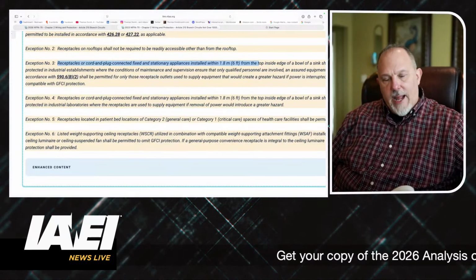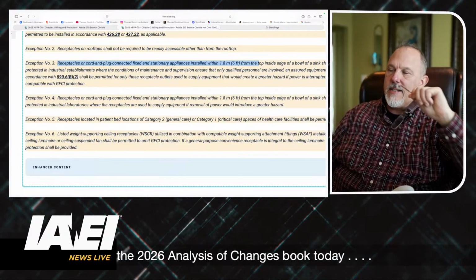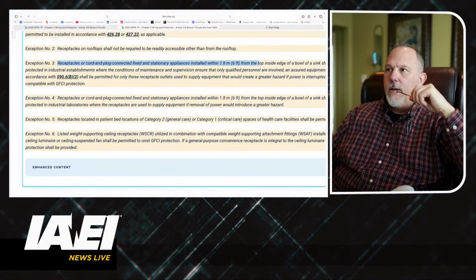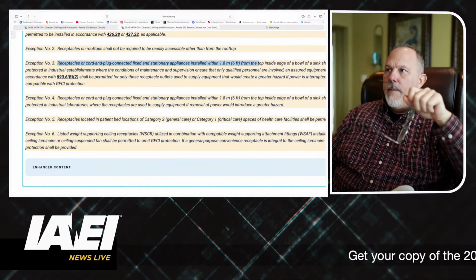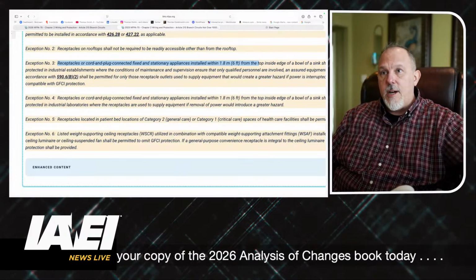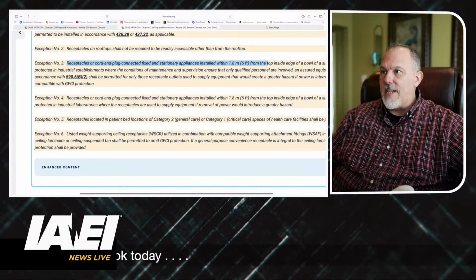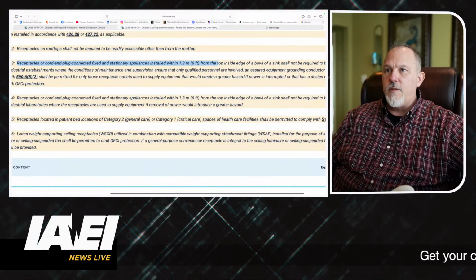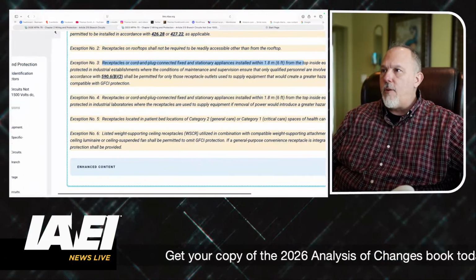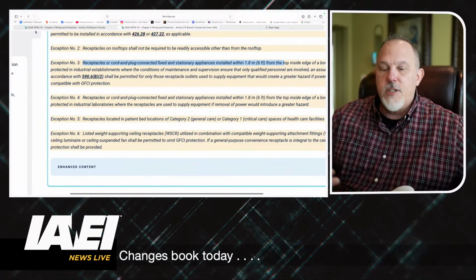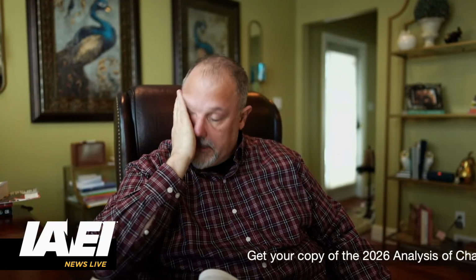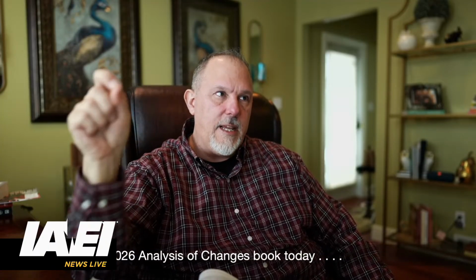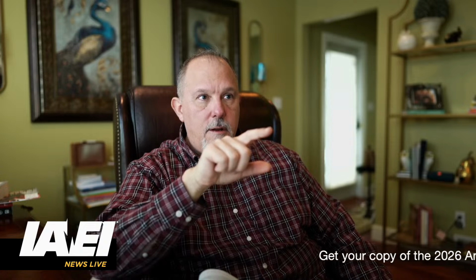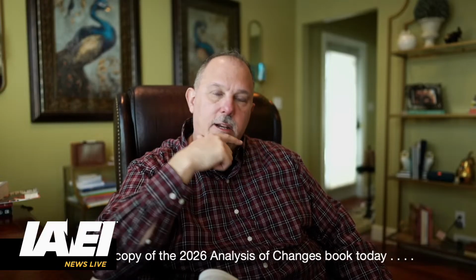So let's break this down. And it was during our task group meeting that I don't know who it was, read this and said, if I just forget about the cord and plug connected fixed and stationary appliances, receptacles installed within 6 foot from the top inside edge of a bowl of a sink shall not be required to be GFCI protected in industrial establishments where the conditions of maintenance and supervision, blah, blah, blah, and an assured equipment grounding program in accordance with it shall be permitted, not required. So the issue was, they said, hold on. If I have a receptacle within 6 foot of a sink, I don't need the GFCI protected in an industrial establishment. And I'm not required to have an assured equipment grounding conductor program. That removes GFCIs from a lot of receptacles.